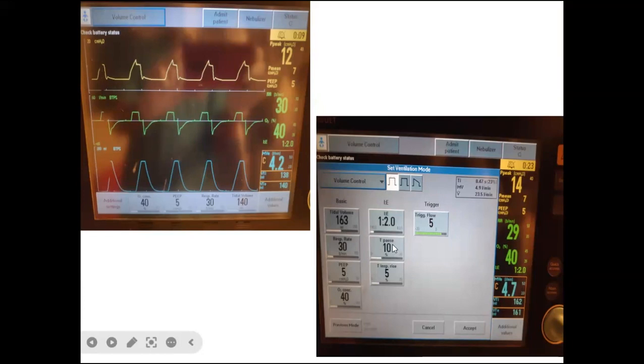T-pause is the time you tell the ventilator that at the end of inspiration, it needs to give a certain amount of pause before switching over to expiration, not inspiration. Can you see here? This is the flow curve. At the end of inspiration, what has happened to your flow? Flow is not becoming negative. What has happened to flow here? Baseline. It is a zero flow state.